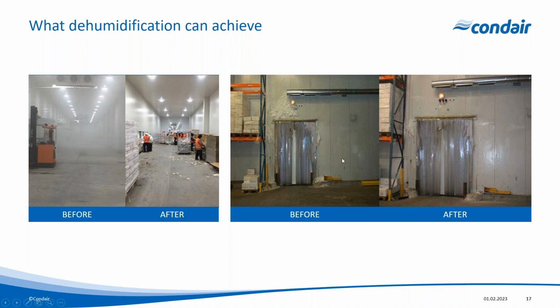In the right-hand picture, we've got the photograph of our door with the accumulation of ice. But you'll notice that there's a duct on top of this. There we go, that's a stainless steel duct. And what's happening is that that duct is attached to a dehumidifier, and dry air is then passed over that doorway. And what happens is the ice goes through the process of sublimation.